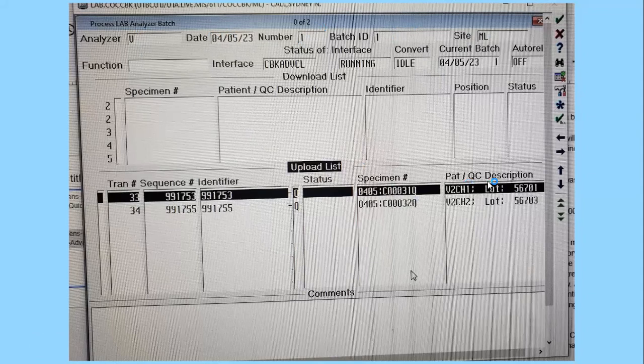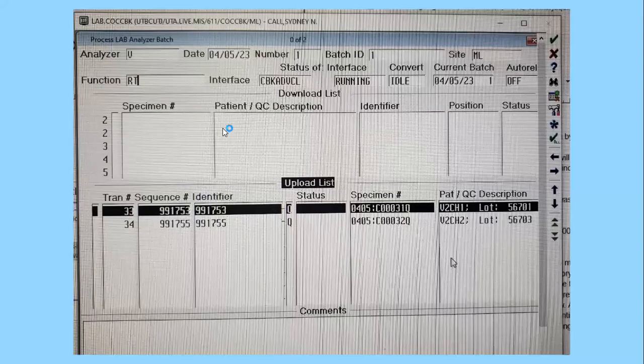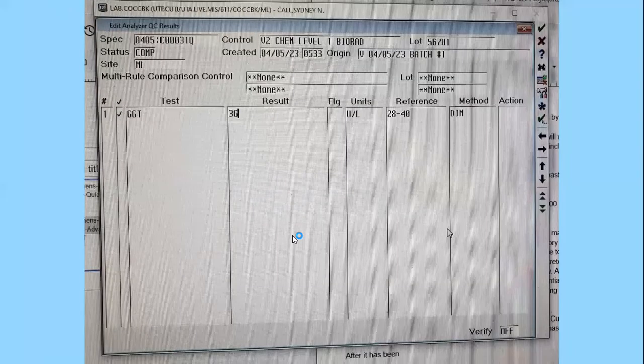You can tell under this QC description, it has the lots, and it will say Vista 1 or Vista 2. This was run on Vista 2. This is Control 1. This is Control 2. So make sure one of these is highlighted in black, and then you're going to go to the function key and type in RT, like so. Make sure everything is capitalized when you're doing this, and then we're going to click enter. And that will bring you up to this Edit Analyzer QC result.